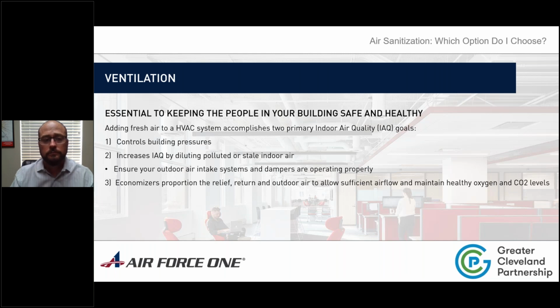Austin, I'd like to add a bit to the ventilation piece. We've talked about this a lot, and I don't think it can be overstated. Many times, if you've had heating or cooling issues, especially in the dead of winter or midsummer when it's hot or humid, the first thing companies will do to try to get control of this is either disable their economizer or minimize the amount of outdoor air going into the space. This typically fixes the issue at the moment, but it exacerbates another issue: indoor air quality. So having your economizer damper, your return damper, and outdoor air dampers verified for proper operation is extremely important.